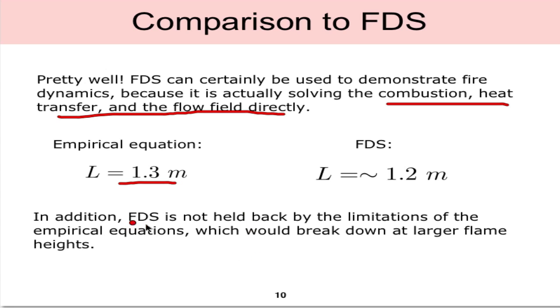Additionally, FDS is not held back or limited like the empirical equation. The empirical equation would break down at larger flame heights outside of that experimental data set, whereas in FDS we could always make a larger heat release rate or larger burning area. Because it's solving for the combustion and physics directly, we'd be able to use it for a wider range of problems.